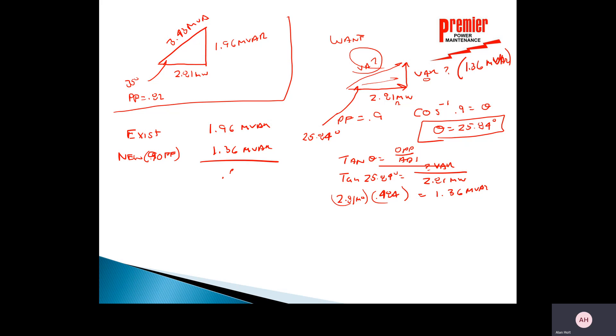The existing system had 1.96 megavars. The new 0.9 power factor system needs only 1.36 megavars. The difference is 1.96 − 1.36 = 0.60 megavars. So 600 kVAR of capacitance is needed to make that correction. That's a good level-three or level-four type question.